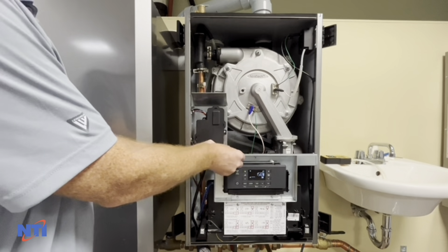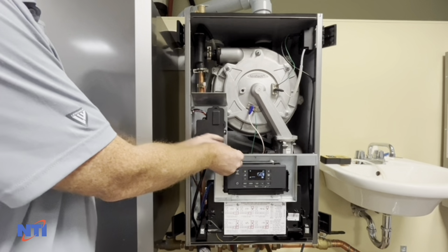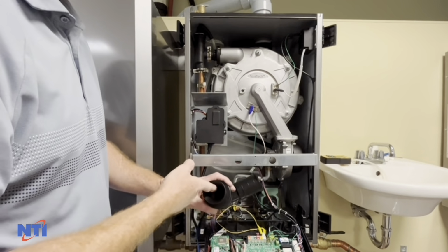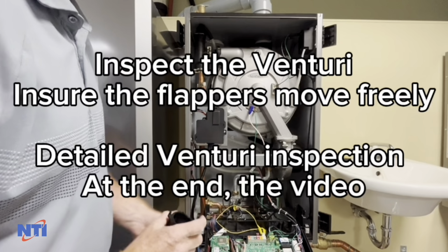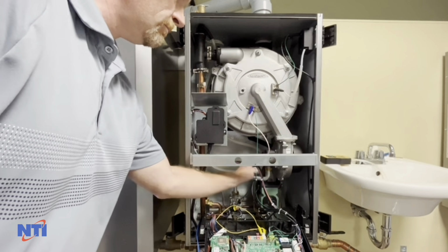Disconnect the power, then inspect the air inlet muffler for dust and debris. Excessive dust or debris may indicate that the burner is plugged. Inspect the Venturi, making sure that both the flappers move freely. Ensure the vents are clear and the burner and combustion chamber are clean before proceeding. Cleaning instructions are at the end of this video.